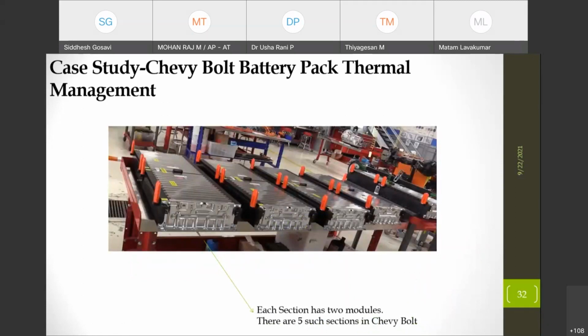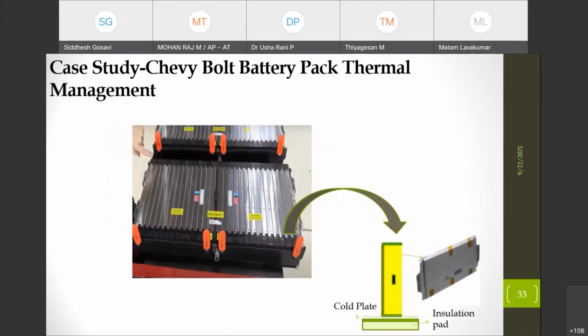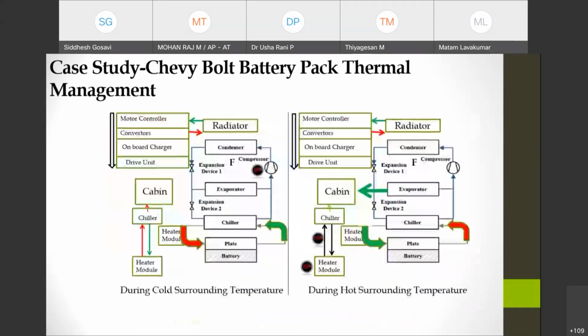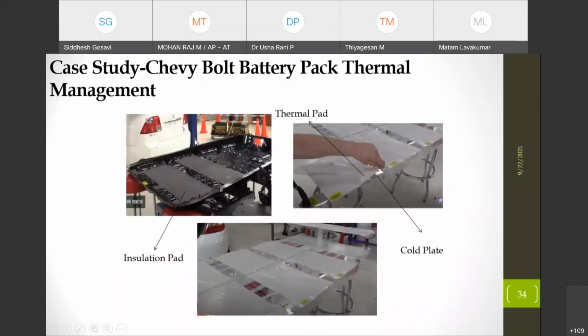So apart from the mechanical arrangement that we were discussing, like the contact, we were discussing how to ensure the contact between my target body and the target medium that is taking away the heat. So the contact needs to be ensured by the mechanical structure and clamping arrangement as well. If you can see the battery pack, once all these modules are done here, there are all these mounting points that will clamp these battery pack modules onto the thermal plate, so that it's always under pressure. Not only is the contact maintained, but the contact is maintained under pressure, so that the heat rejection shall be very effective.